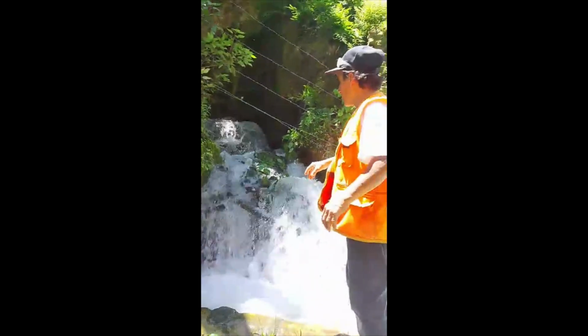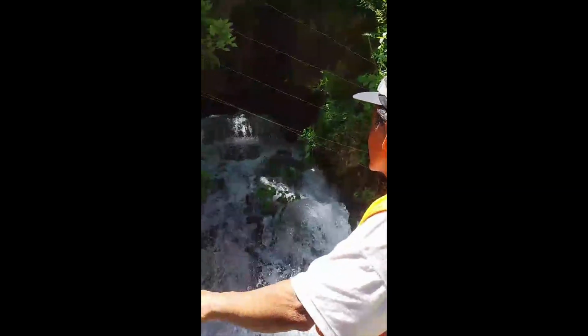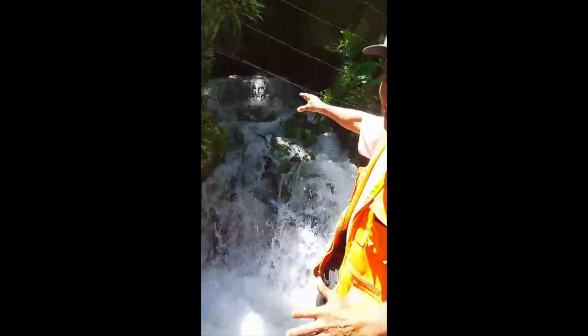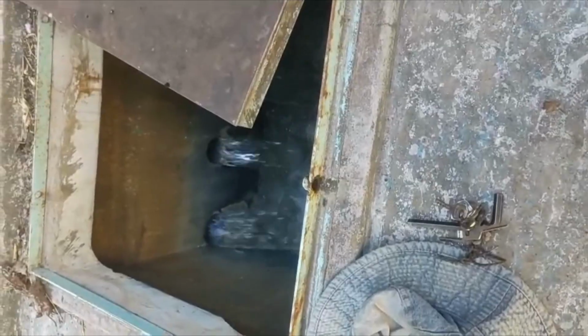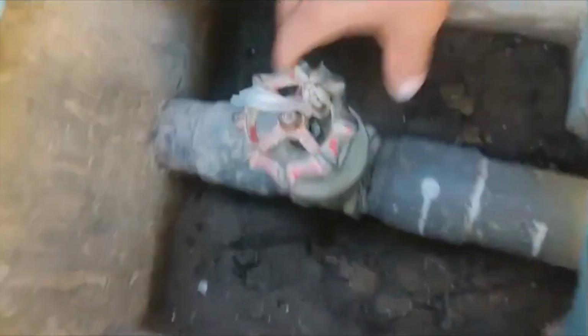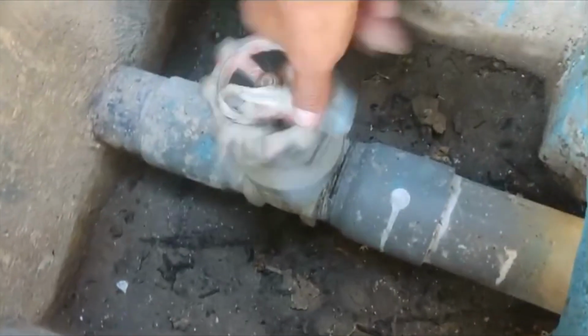Now, regarding the captación, compared to the reservoir, more risk factors were found here that should really be addressed. This includes not being fenced off, allowing any person or animal entering the area, organic material found inside the system, leaks and cracks in the pipes and main structure itself, and so on. This is a relatively old captación, about 50 years old, that presents several of these risks because of the constant wear and tear of its operation. While there are ways that these issues can be addressed in the short term, it is clear that this captación will have to be rebuilt from scratch in order to prevent the contamination of water.